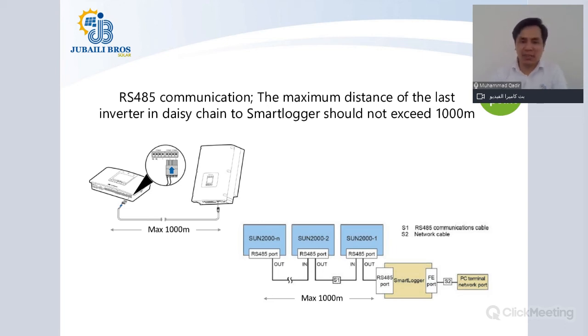For RS485 communication, the maximum distance from the smart logger to the last inverter should not exceed 1000 meters. Using RS485 communication, as I said, you can connect a maximum of 30 solar inverters to one COM port. From the smart logger to the last inverter, let's say the 30th inverter in the max scenario, it shouldn't be more than 1000 meters, 1 kilometer. So please make sure that this distance is taken care of when you are installing our HUAWEI solar inverters. A distance of more than 1000 meters will result in distortion of your communication signals.